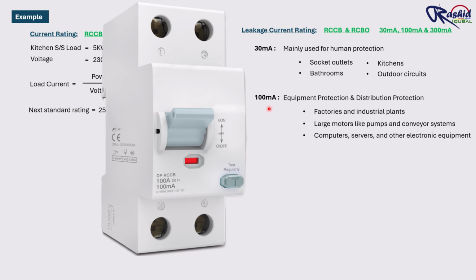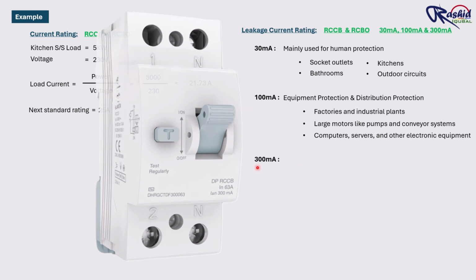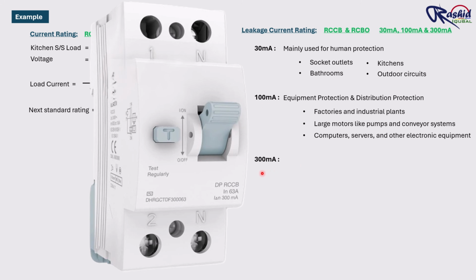Now let's understand 300 mA RCCB. A 300 mA RCCB is mainly used for fire protection. Suppose a leakage current continuously flows through the building structure, cable tray or other materials. This continuous leakage generates heat. Over time, the heat can damage insulation further and may even start a fire. So a 300 mA RCCB detects this higher leakage current and disconnects the supply before it becomes a serious fire hazard.